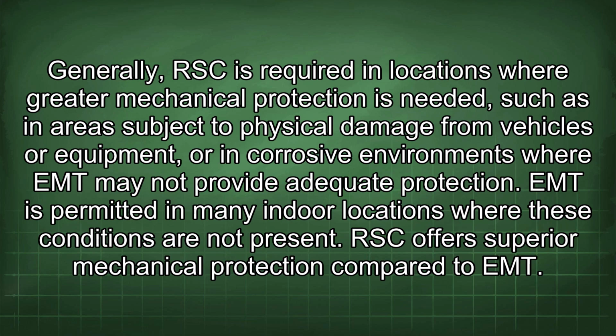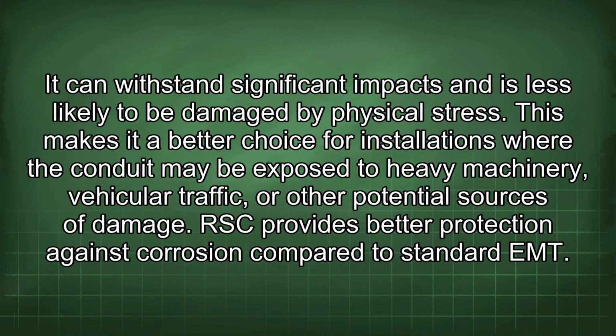RSC offers superior mechanical protection compared to EMT. It can withstand significant impacts and is less likely to be damaged by physical stress. This makes it a better choice for installations where the conduit may be exposed to heavy machinery, vehicular traffic, or other potential sources of damage.